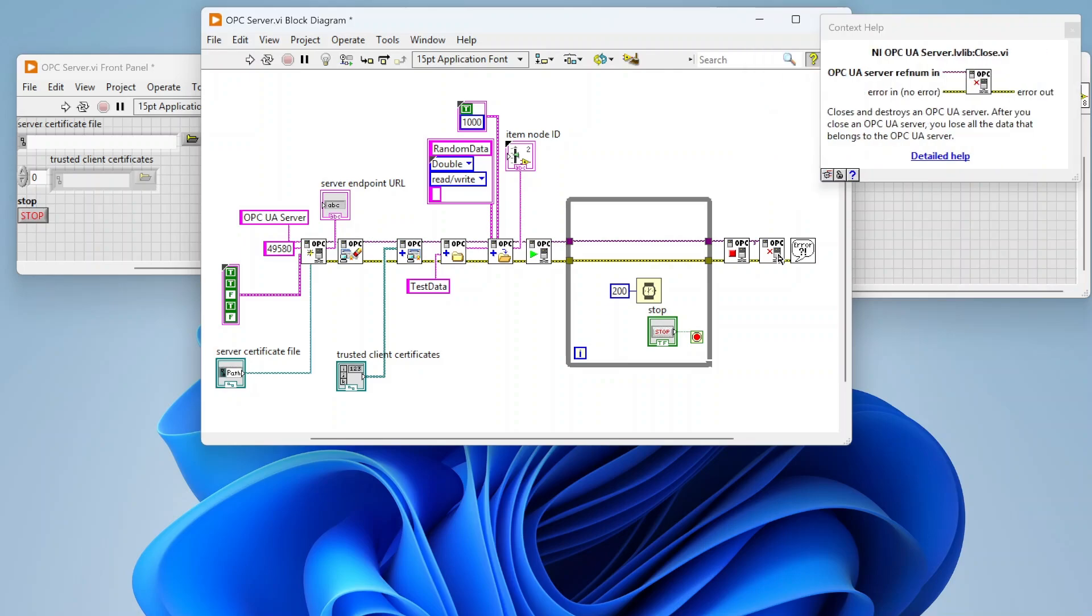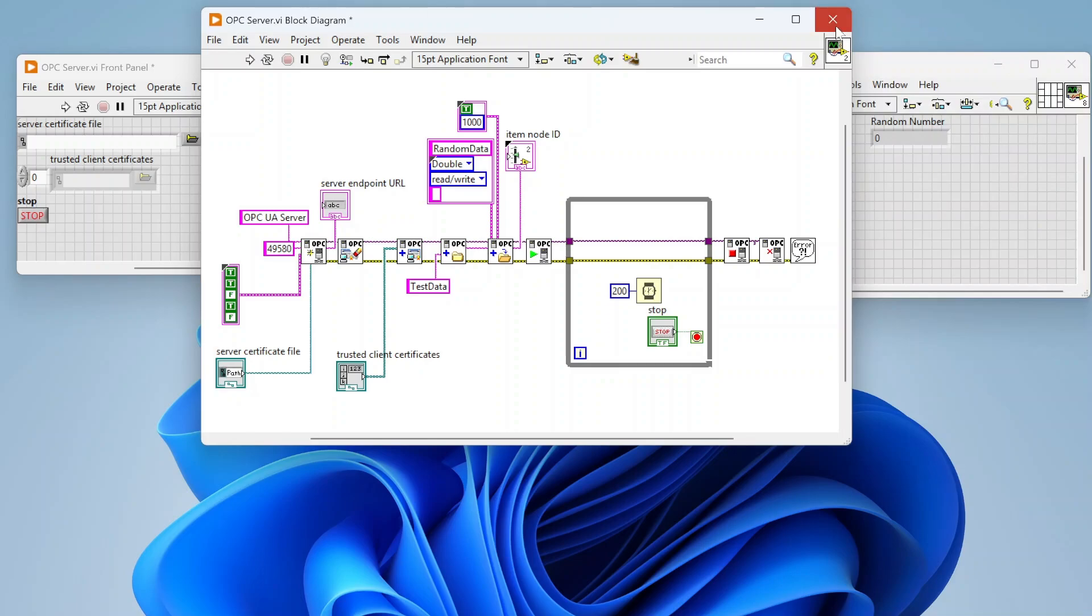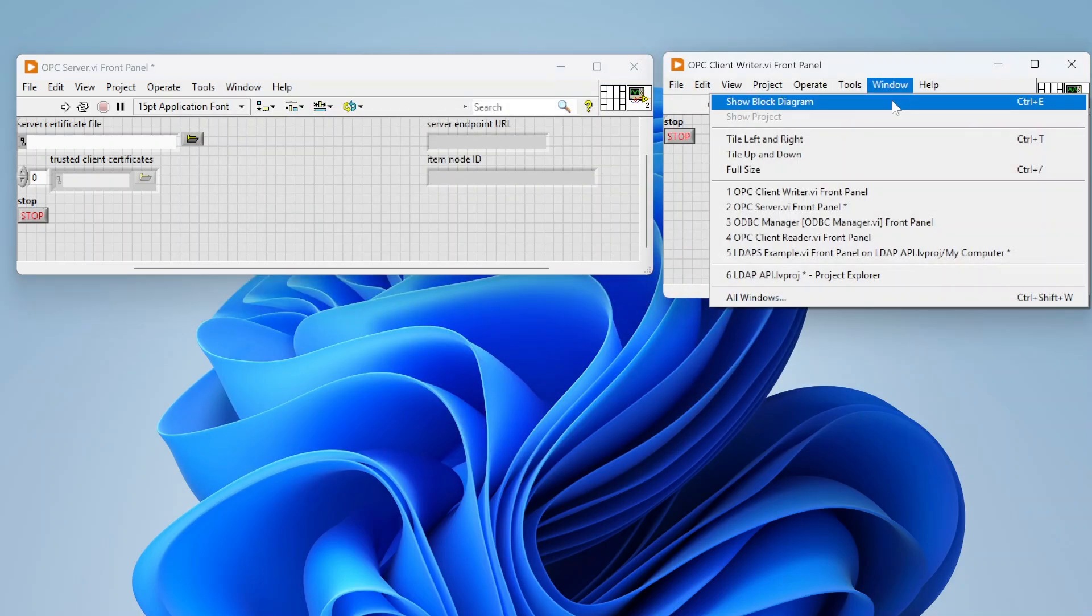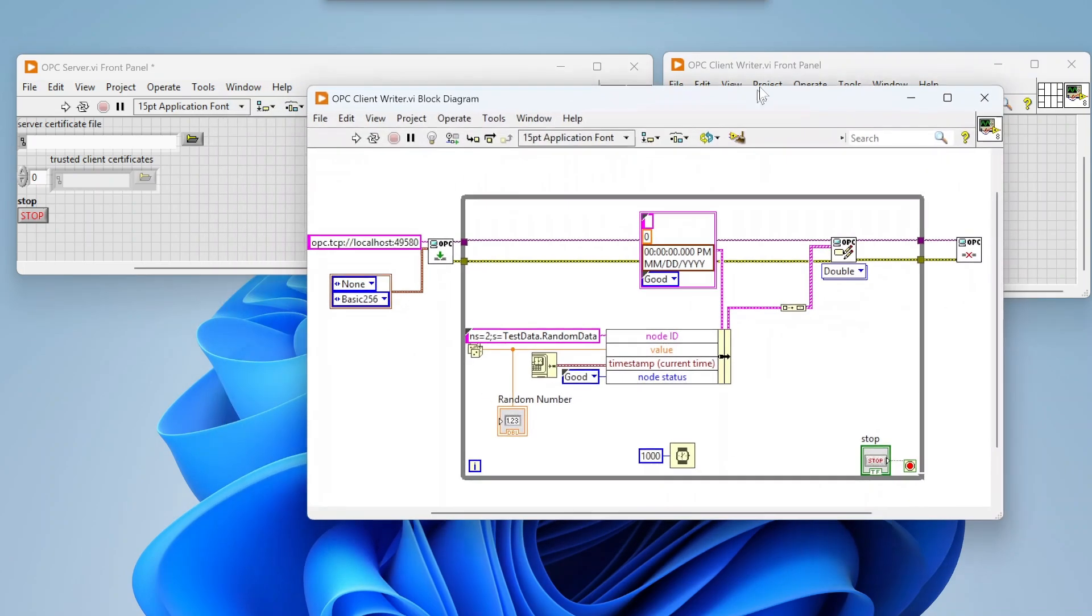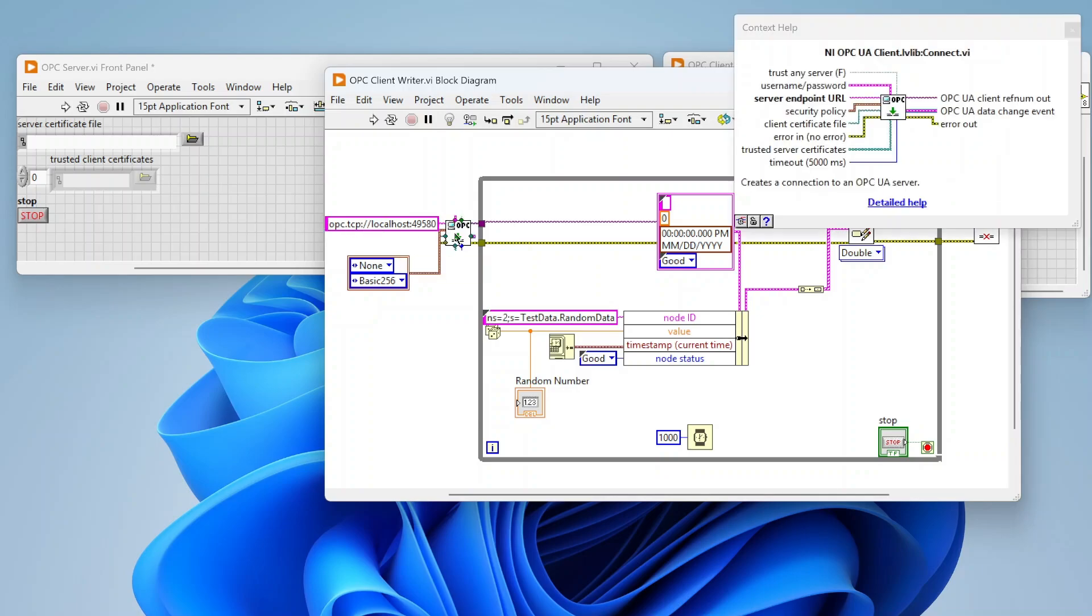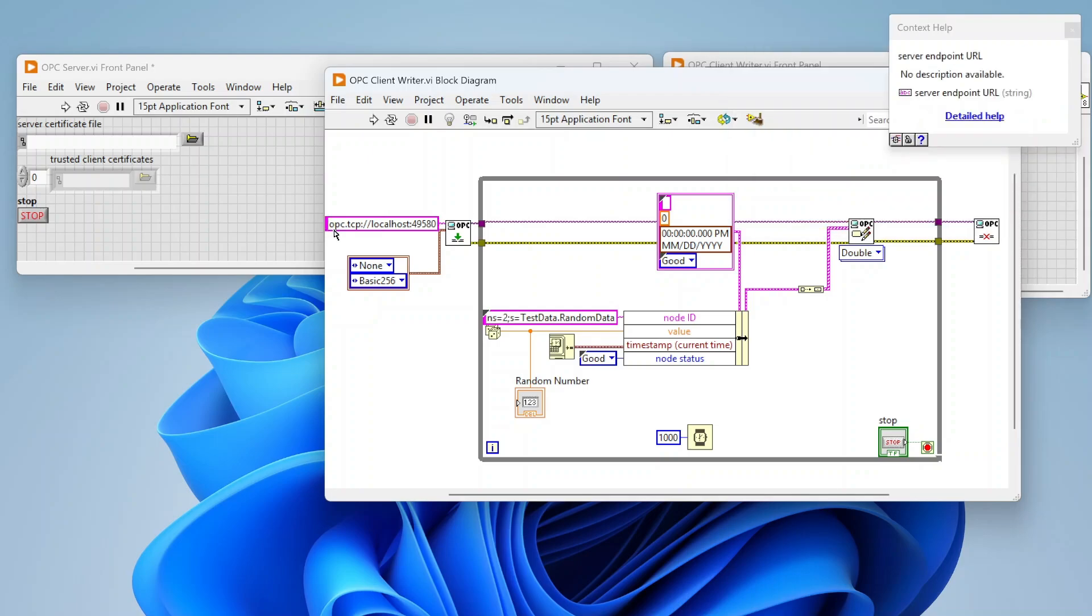That's kind of it on the server side. I've created a writer and this is pretty simple. We're going to connect to our OPC UA client connect. We're going to connect to this location using this format: opc.tcp colon slash slash your IP or URL DNS name, however you're finding the device, and then another colon and then the port you're connecting to.